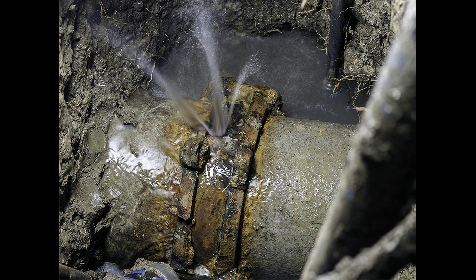In the event of a water main break, the city has 5,427 valves that can be used to isolate sections of the water distribution system so repairs can be made. The valves are tested by the city once every 5 years. A broken water main is repaired by wrapping a stainless steel sleeve around the break, sealing the leak.